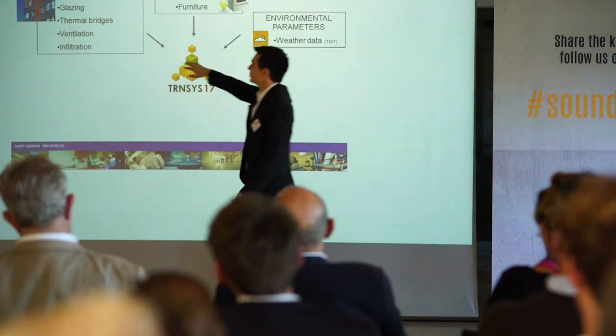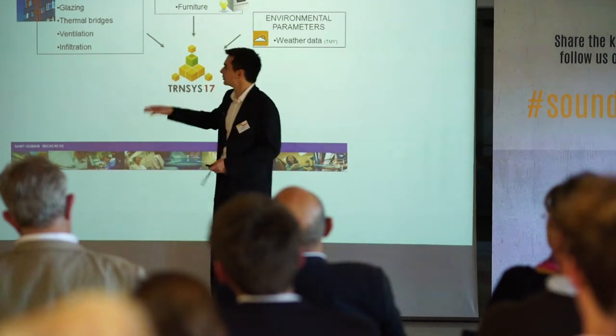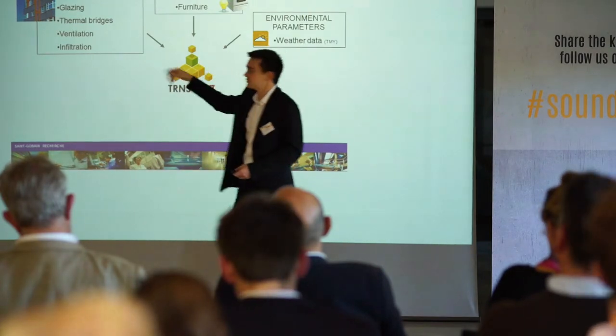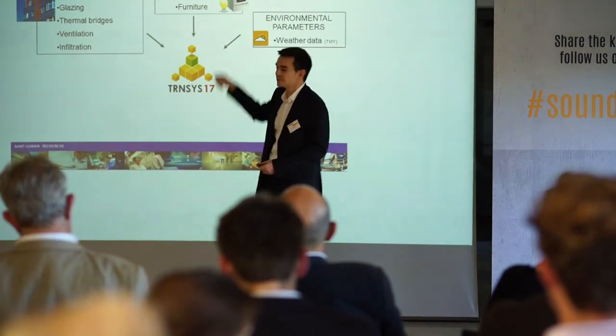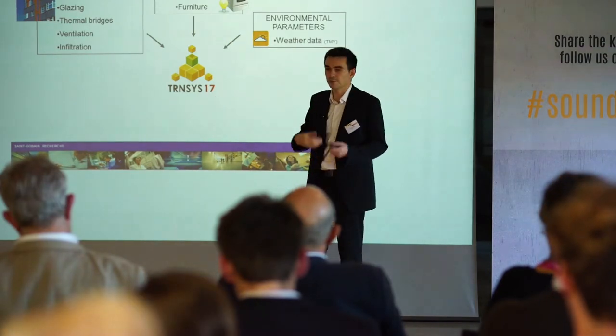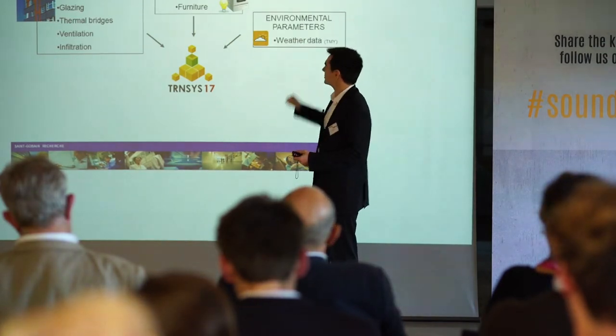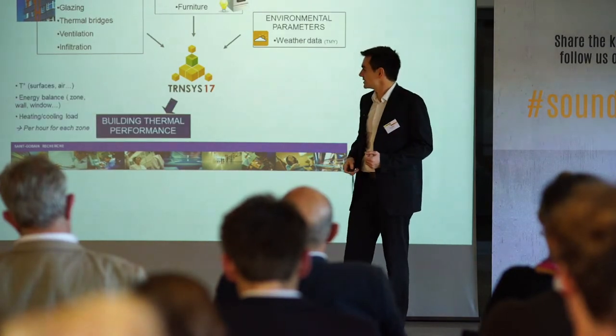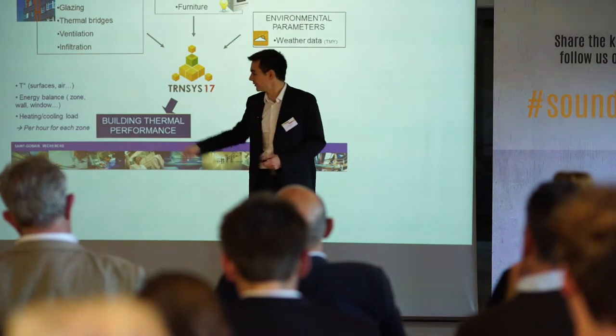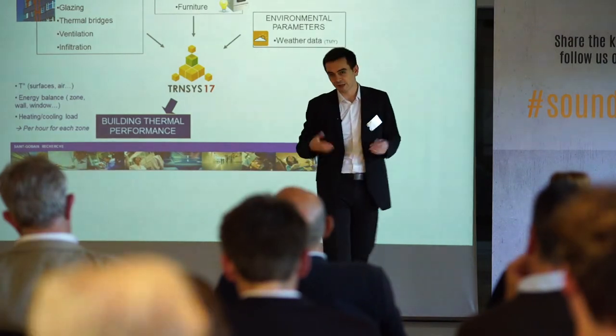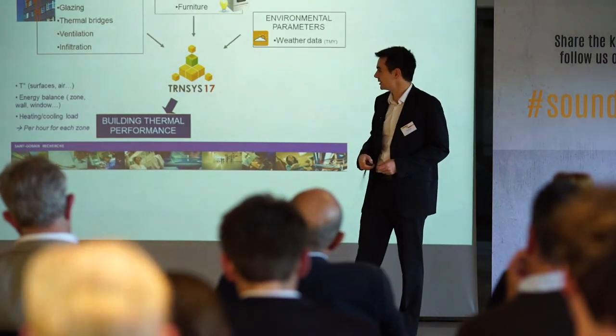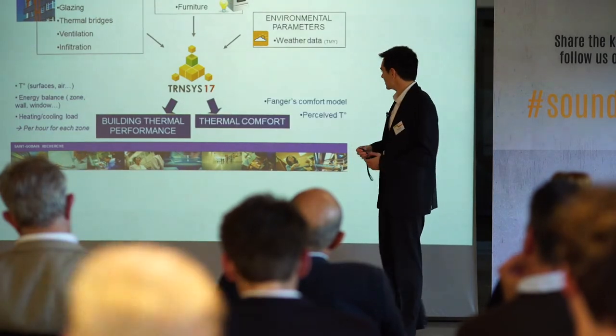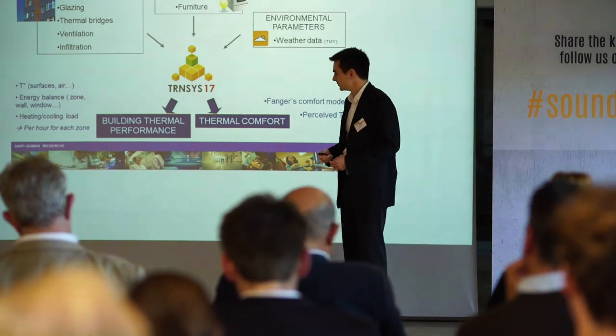You give TRNSYS the building parameters: the surface area of each wall, the position of glazing, the type of glazing, the thermal bridges, the ventilation and infiltration. You also give the gains: the occupancy, the equipment, the activity in the building, and weather data. Thanks to all these data, TRNSYS is able to compute the building's thermal performance — the air temperature in each room, the heating and cooling loads, and also the thermal comfort inside the building.